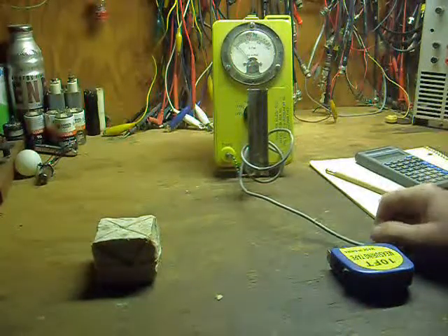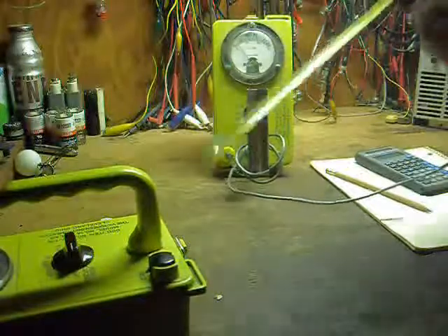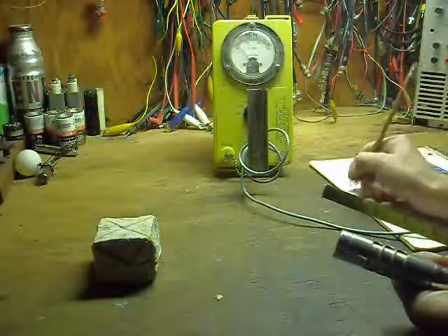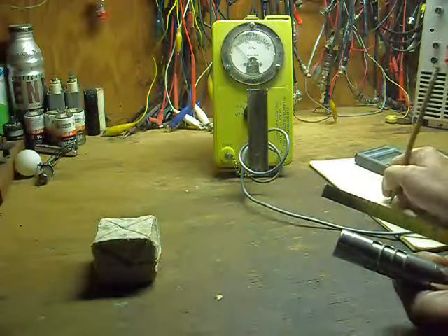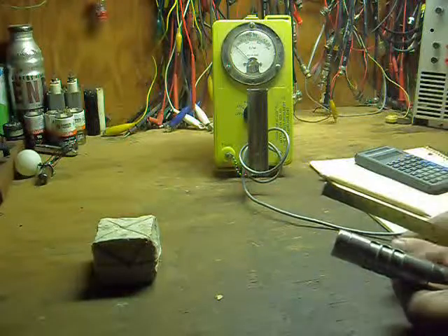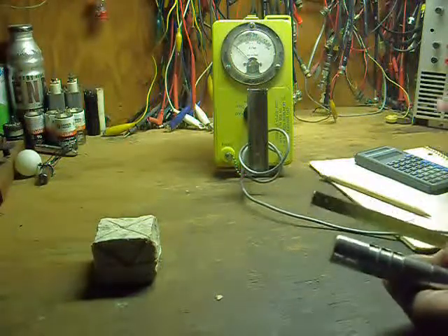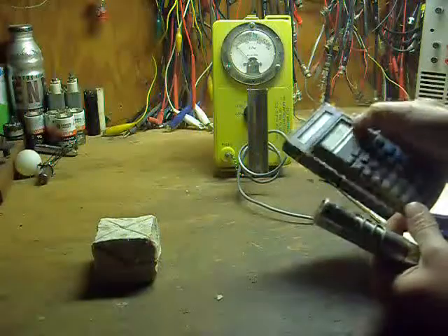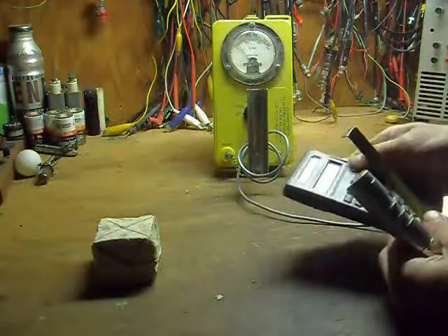When the object is larger or more radioactive, then the distance the reading is taken should be larger to get a more accurate reading. When you log those readings, you should log the measurement taken, its exact distance from the radioactive object, along with the measurement of the level of background radiation a considerable distance from the object. That will allow someone to strictly take your figures and calculate the radioactivity of the object you are cataloging in a quantitative fashion.